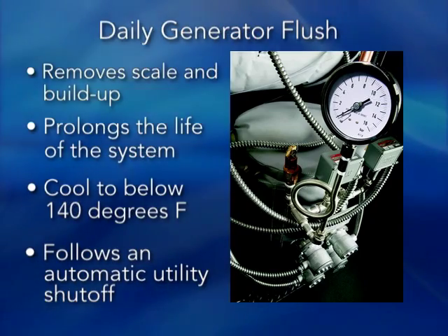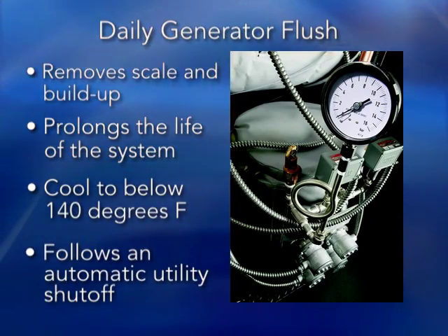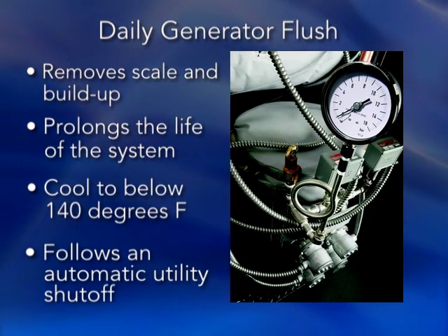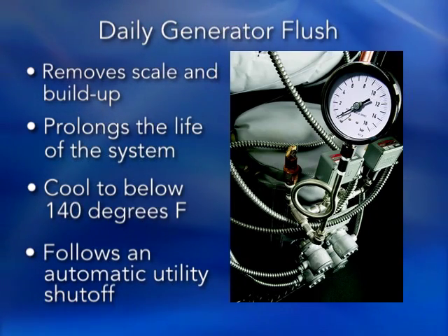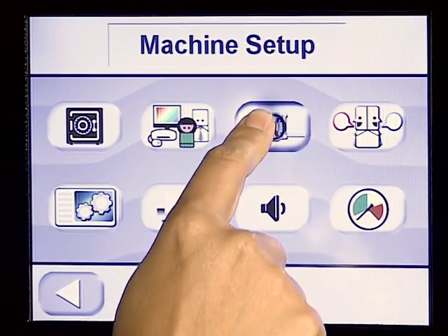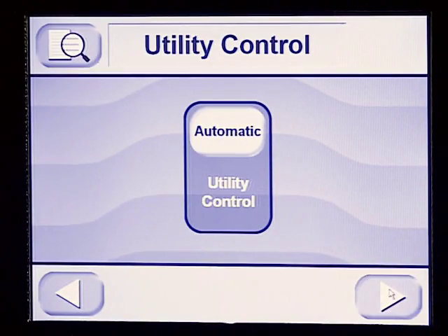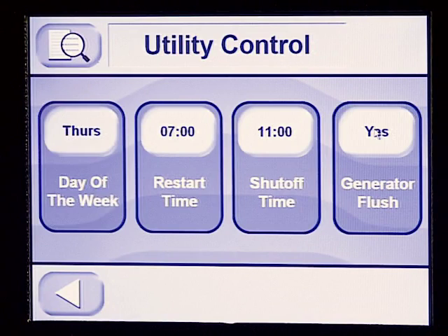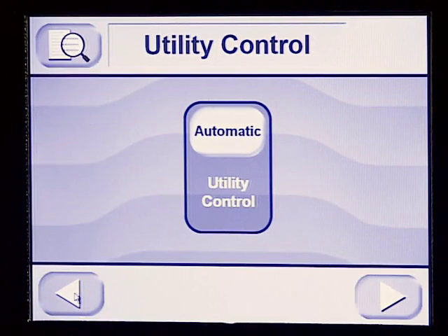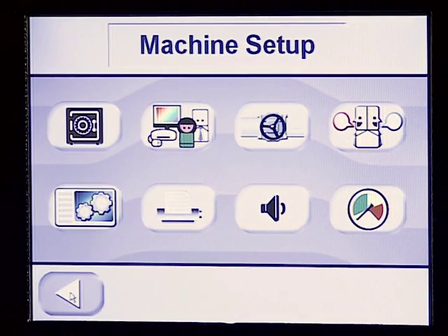We recommend that you program the automatic utilities control to turn off the sterilizer utilities daily for at least 6 to 8 hours for an automatic generator flush to occur. Navigate to the Utilities Control screen from the Machine Setup screen. If the generator flush says Yes, then your sterilizer is set to perform the flush. If the button says No, press it until it says Yes. Press Exit to return to the Machine Setup screen. The flush has a duration of 3 minutes. If the generator has not cooled sufficiently before the automatic utility restart begins, the flush will not occur.